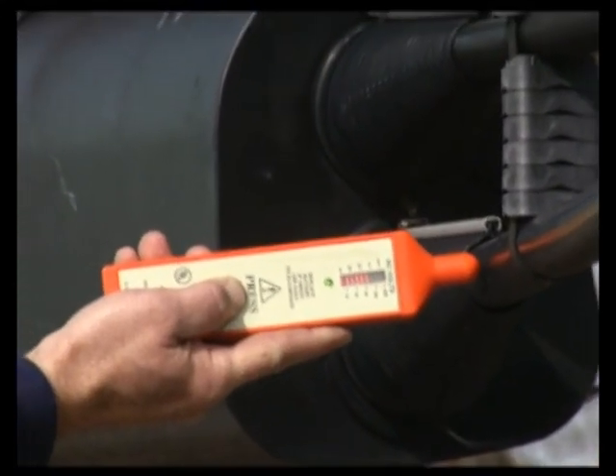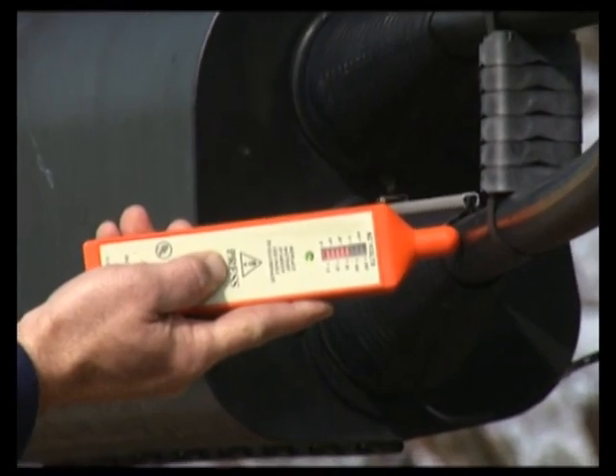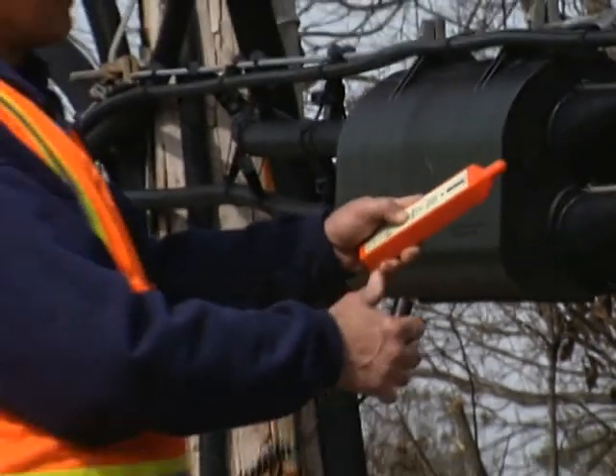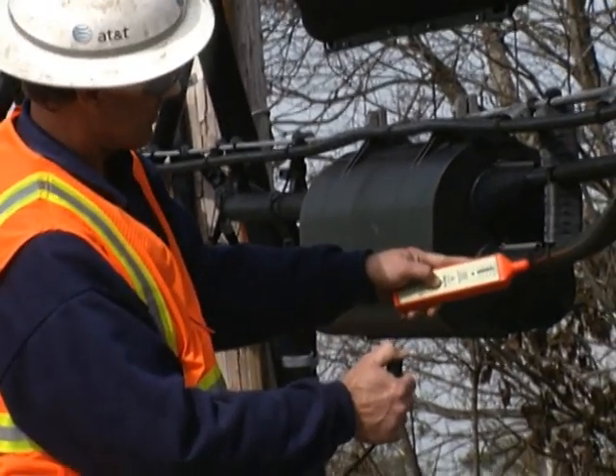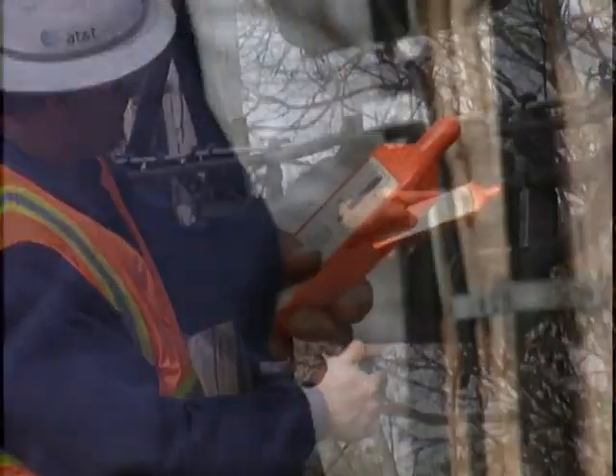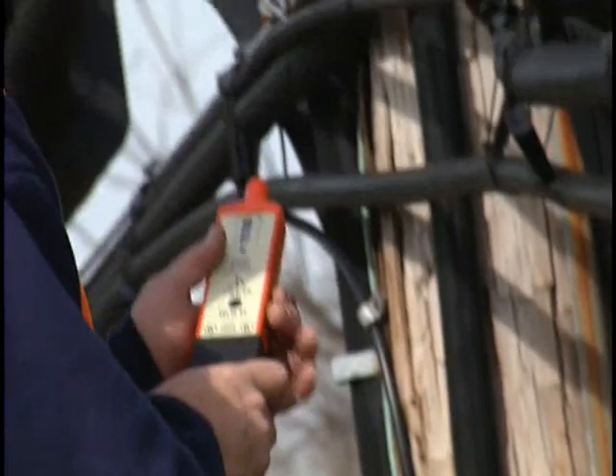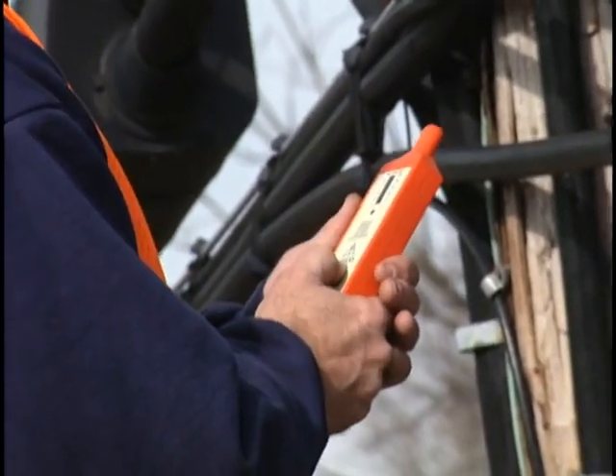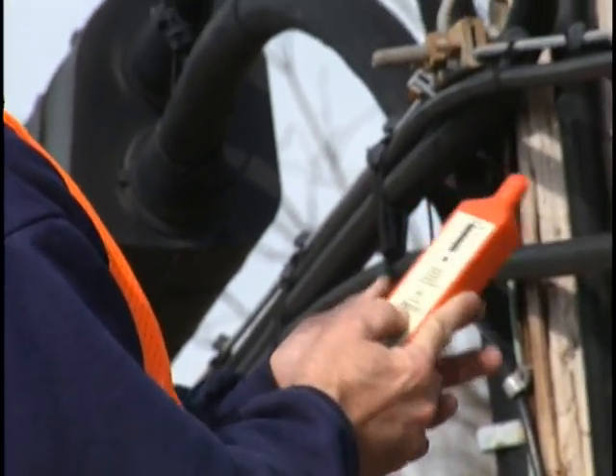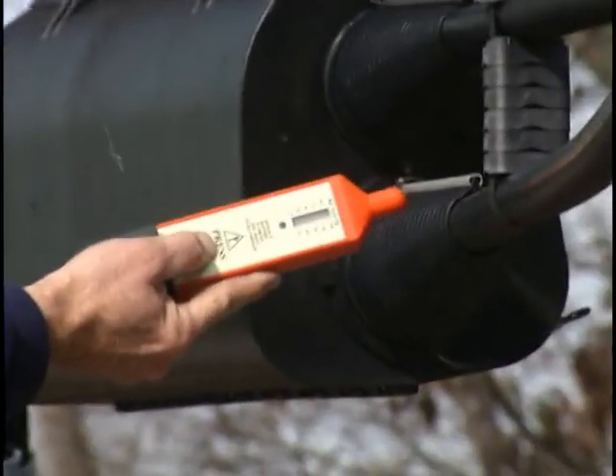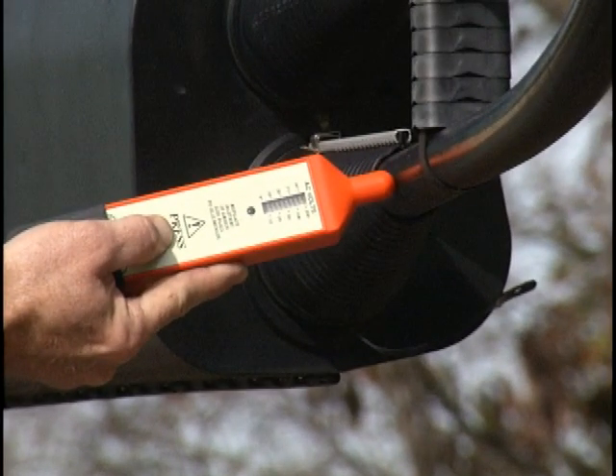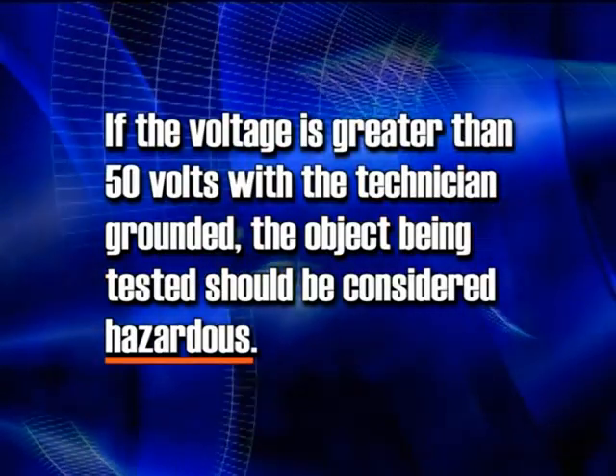Note that when testing from the side, the technician is not shielded from the E field by the cable or strand. Observe what happens when the technician grounds himself while testing this strand. Now the test will be repeated using the conductive cap. Remember, if the voltage is greater than 50 volts with the technician grounded, the object being tested should be considered hazardous.